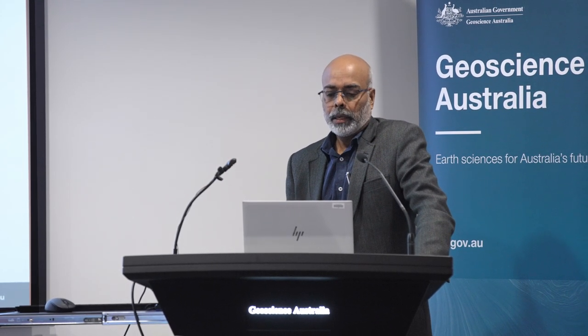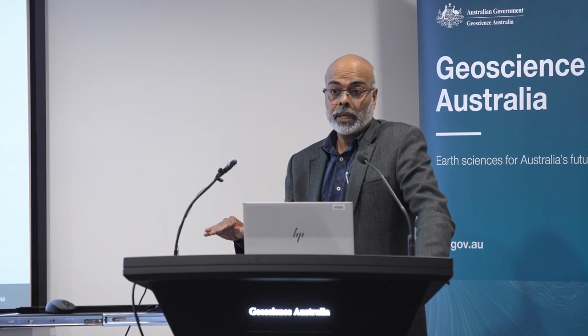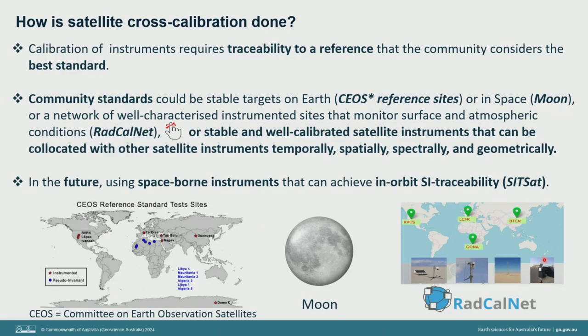This is just a quick primer on how cross-calibration is done. The key to cross-calibration is having a known standard as reference to provide traceability. Often the reference is an SI traceable reference—the international system of units—a term used in EO. Such a standard could be a stable natural target on Earth, like the PICS targets mentioned previously. It could also be something in space, like the moon, which has stable illumination that can be used as a calibration target for a number of sensors. Or it could be a set of well-characterized and instrumented ground sites with stated uncertainty for the measurements happening on the ground.